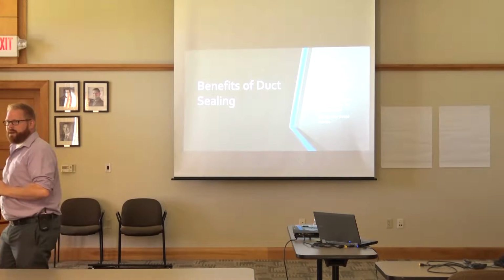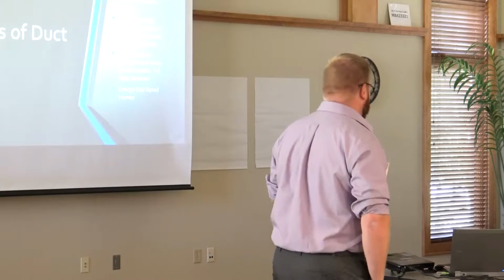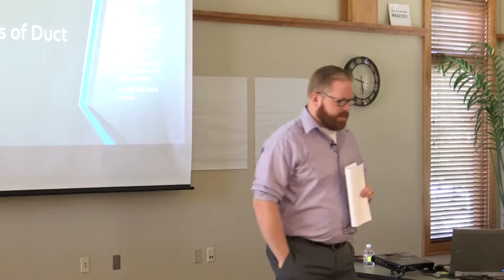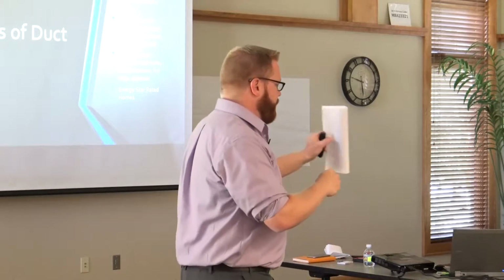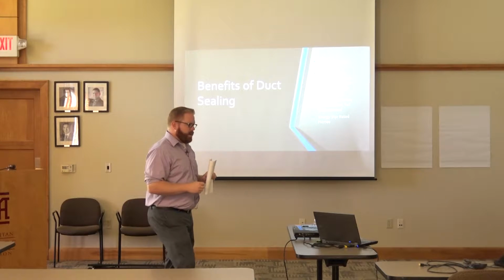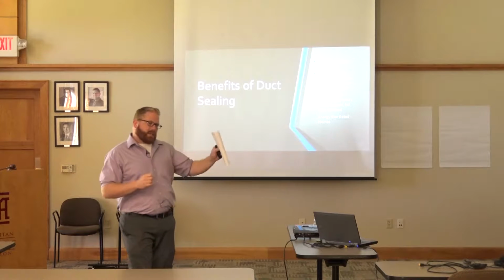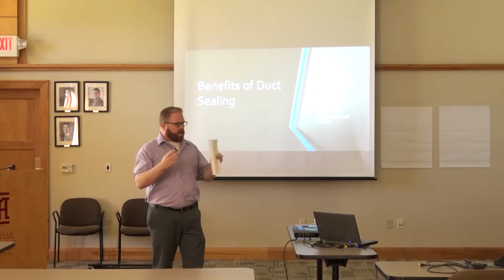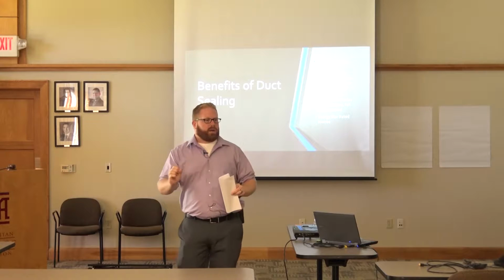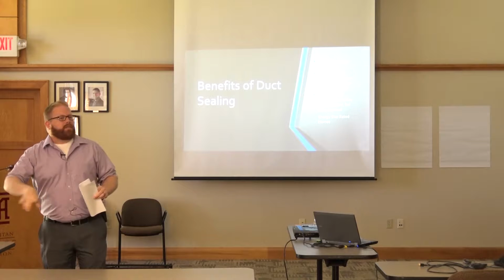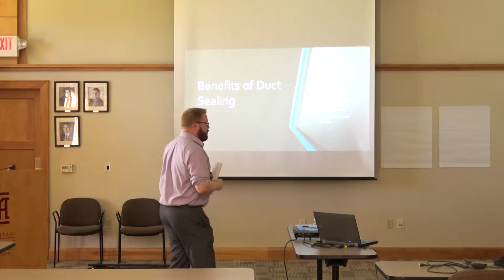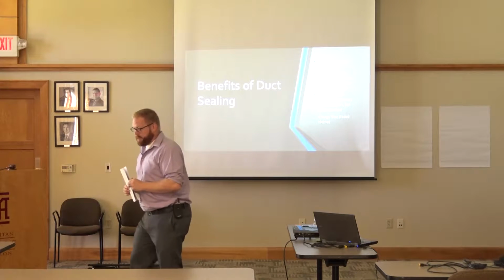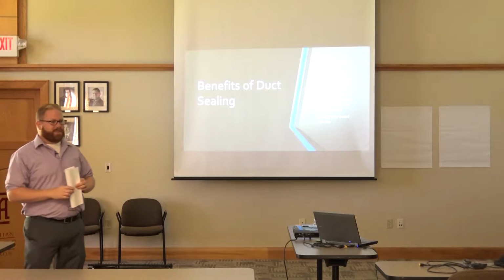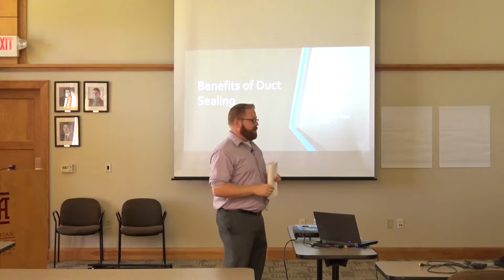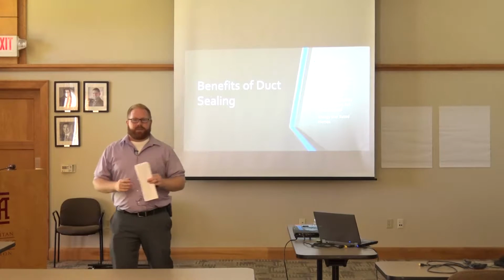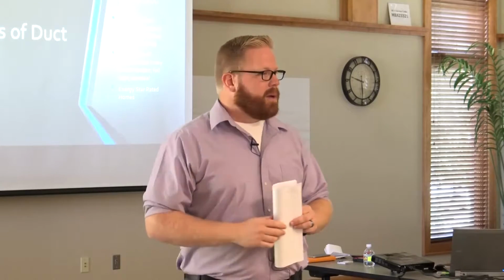Has anybody heard of AeroSeal before? It's a fairly new product in the industry. Basically, it's a big machine that introduces a chemical, almost like a gum, xanthan gum I believe is one of the properties, into the ductwork. It pressurizes the ductwork, and wherever there are cracks, gaps, or seals less than about the size of a quarter, that material seals it up from the interior rather than taping it or using mastic. It's a new way to approach duct sealing, very popular in southern climates where air conditioning runs 11 months a year. It's becoming popular for attic applications too, so you don't have to go up in a 130-140 degree attic and manually tape ductwork. It works really well.